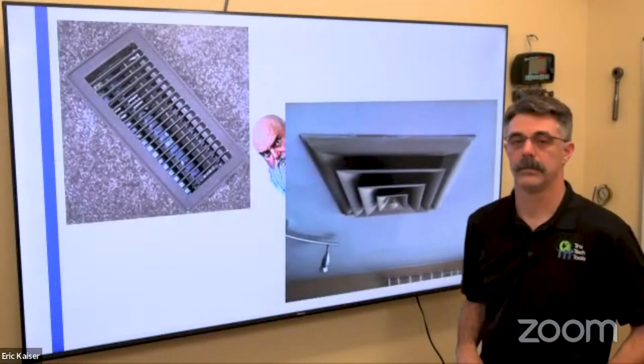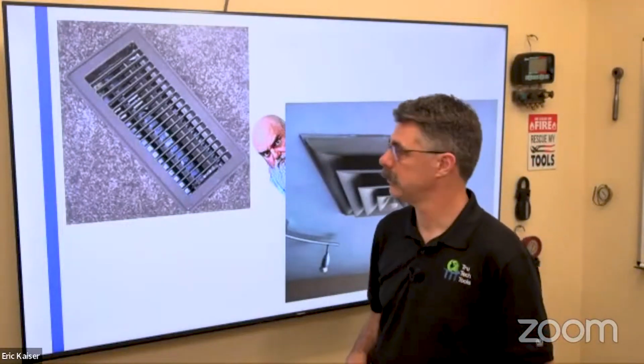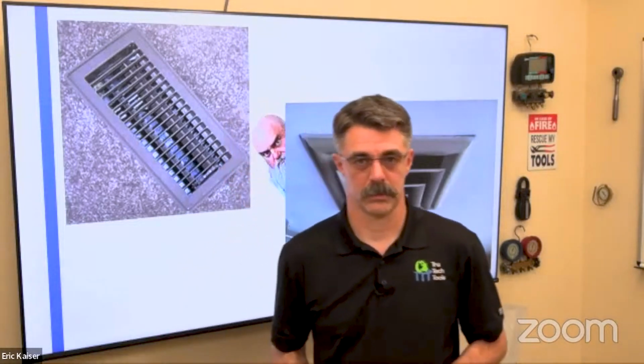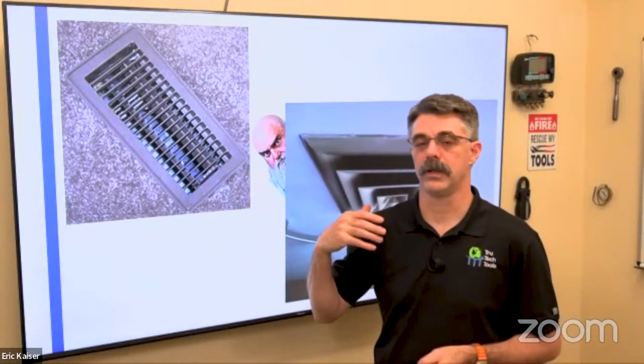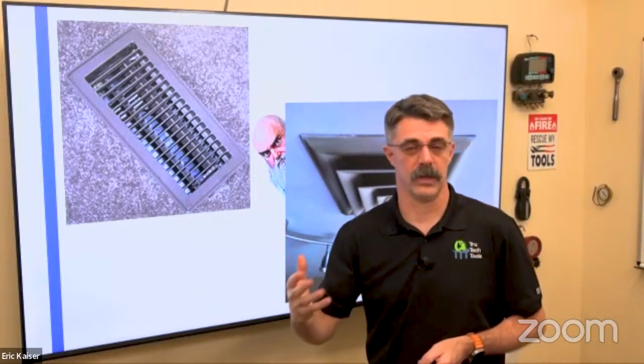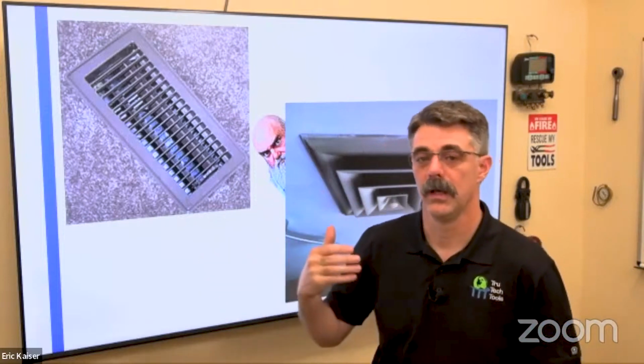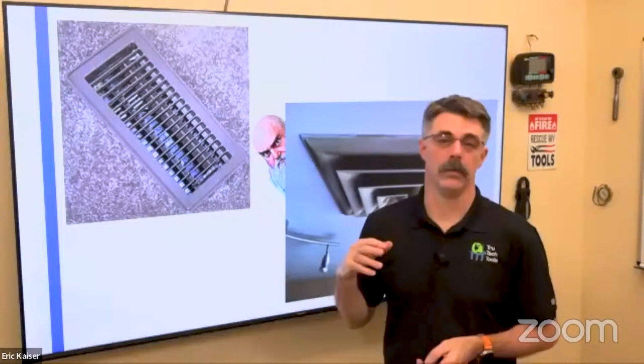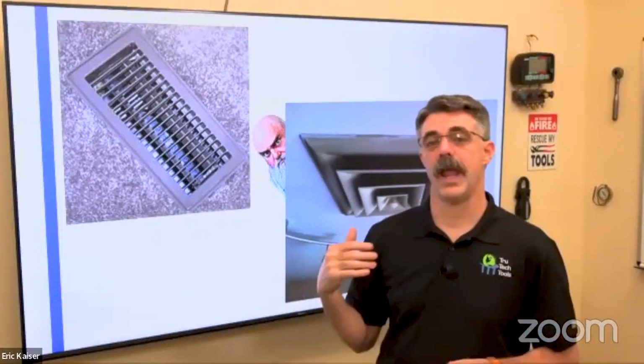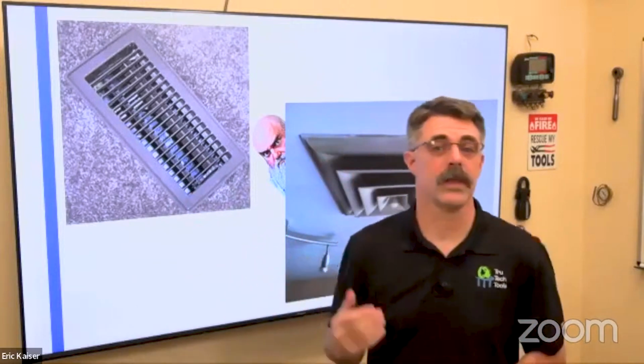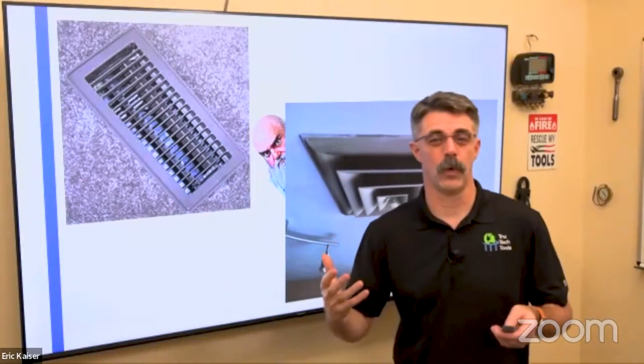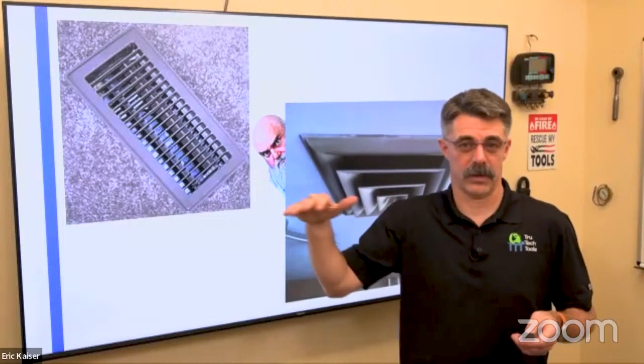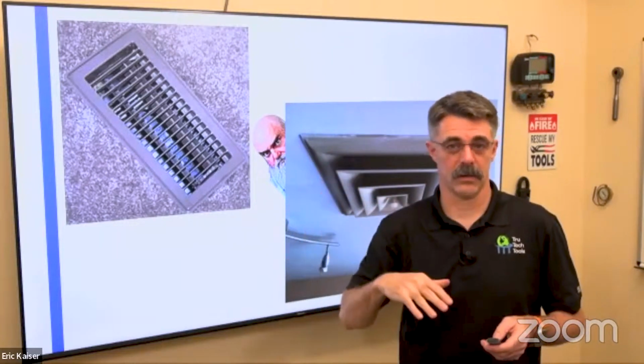All right, let's talk about register placement. Okay, so what we really want to do with registers is put conditioned air, actually over-conditioned air, into the room. It's going to be hotter coming out of the heating than we want the room to be, and that warms the air up in the room. But that air does something else. That air transfers heat into surfaces, which is really the first thing we want to concentrate on heating up, because there are enough surfaces in the room that it will heat the air in the room.